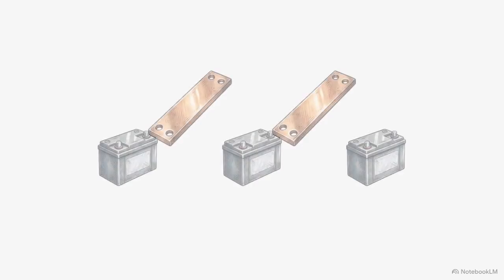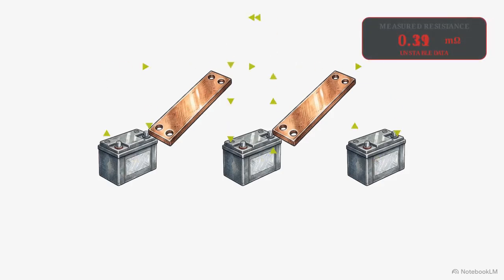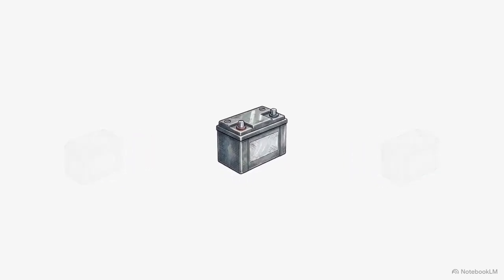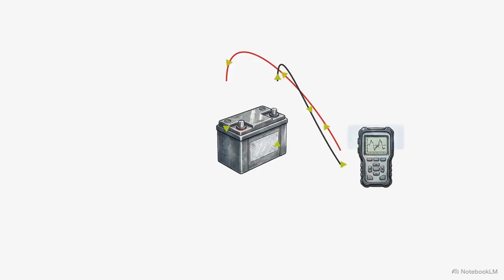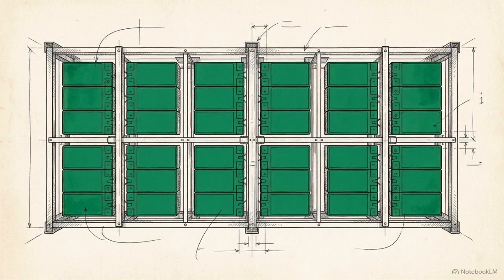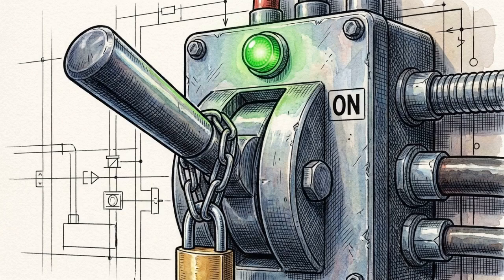Testing the internal resistance of the cells requires an essential mechanical step first. The individual cell links must be physically disconnected. Measuring internal resistance across a fully connected bank yields dangerously invalid data, as the parallel electrical pathways mask the true resistance of the individual unit. This granular cell-by-cell mapping establishes the static, chemical, and electrical baseline. Only when this baseline is verified can we safely authorize dynamic load testing.